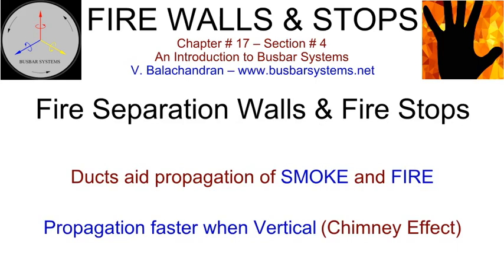Metal enclosed air insulated bus, as with any other duct such as a ventilation duct, can aid in the propagation of smoke and fire from one location to another. The propagation is faster when the configuration is vertical, aided by the chimney effect. There have been instances when the smoke from the fire on a generator transformer, traveling to the generator terminals through the isolated phase bus, has initiated fire and damaged the generator.